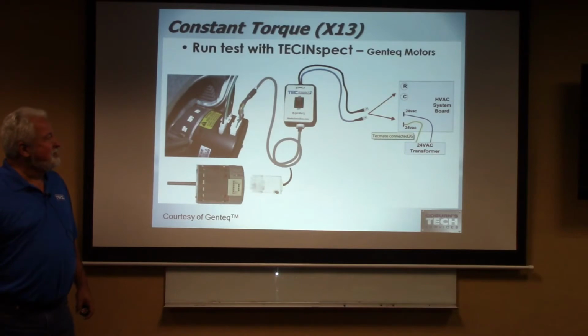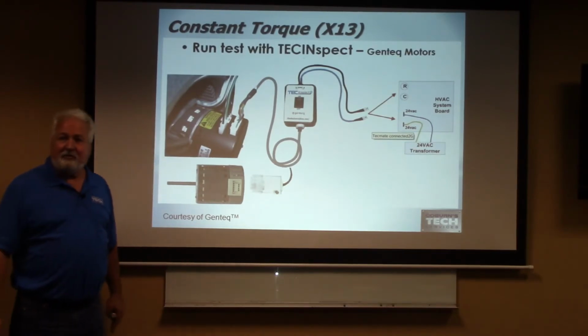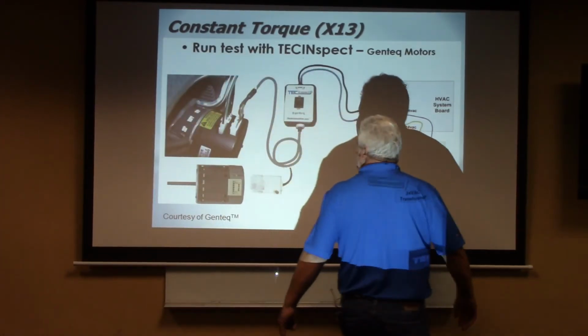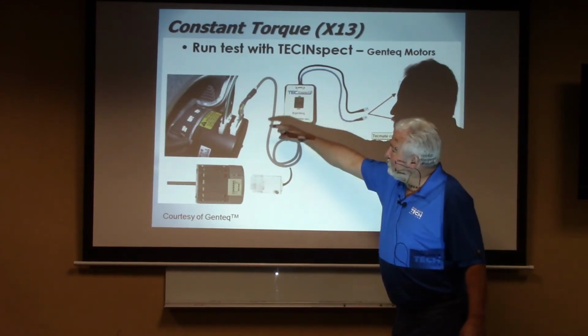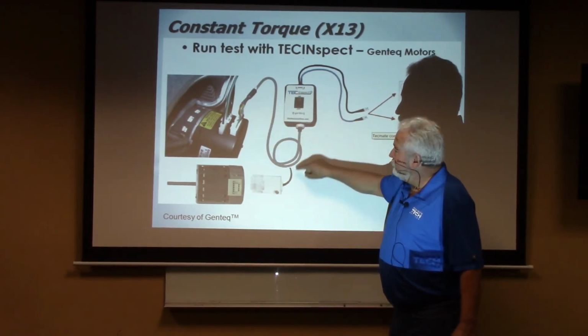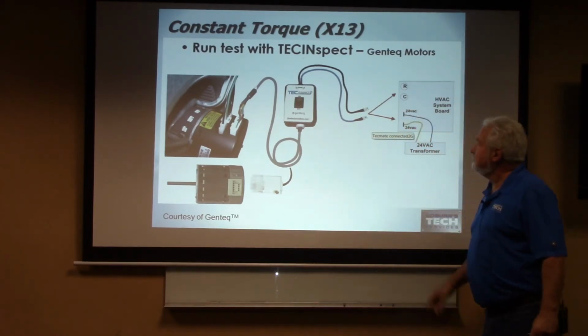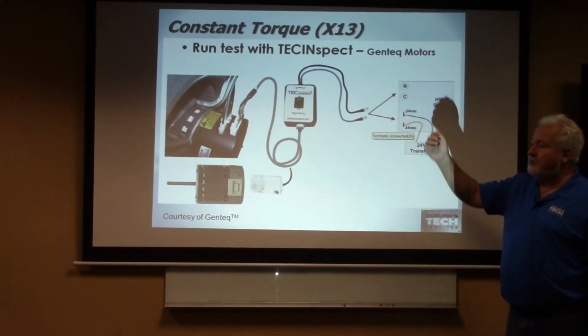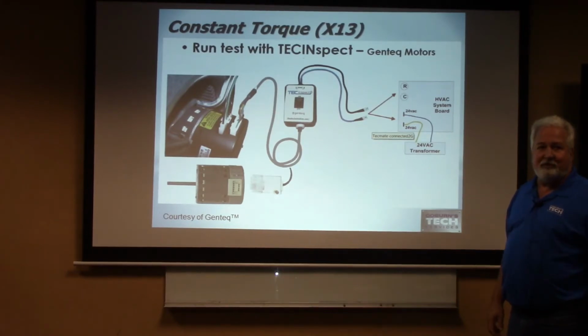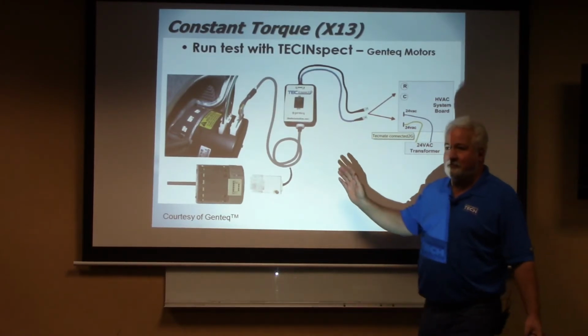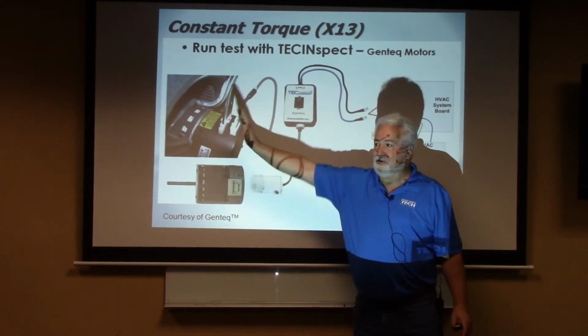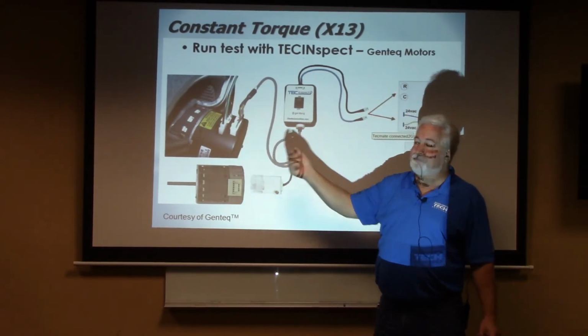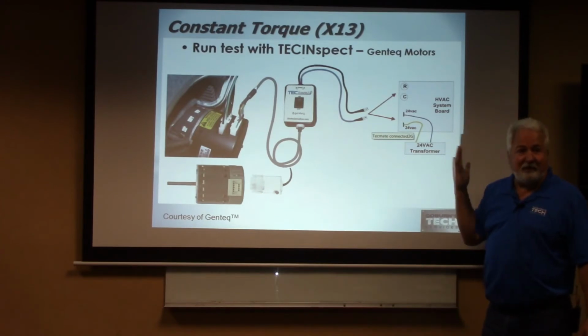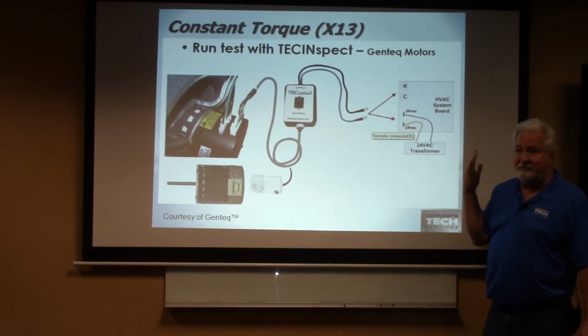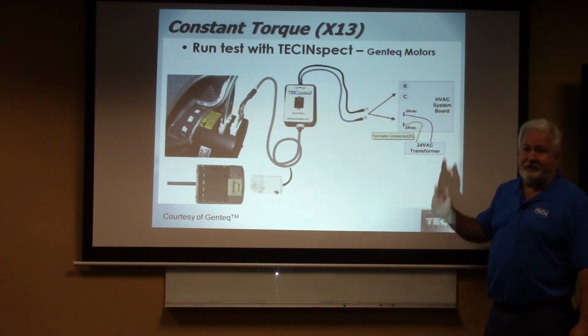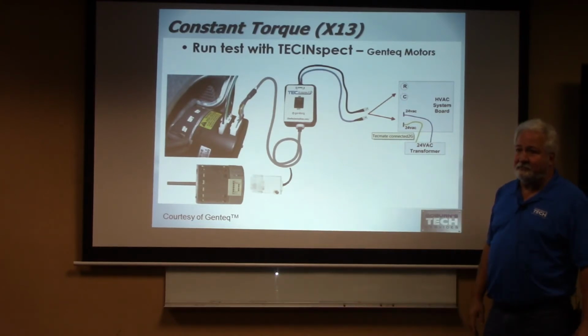Yeah, I got you. TECInspect, here's that motor tester. If I just pull the communicating part out, put the TECInspect into that, connect that to 24 volts and press on, and the motor runs, what's good? The motor's good. That's good. Does that make sense? Something over here may be not sending us that signal. Does that make sense? Cool. All right. How easy is that? What do you need?